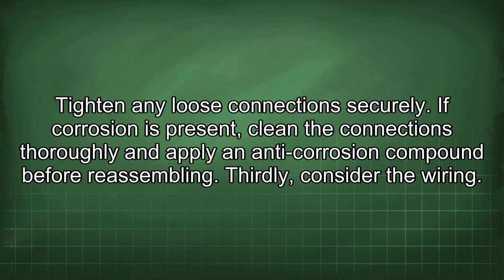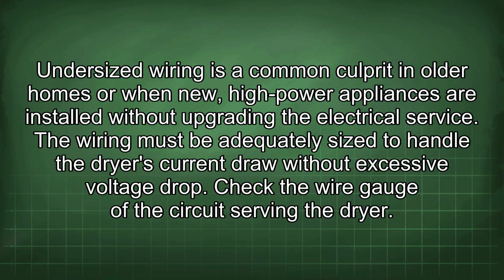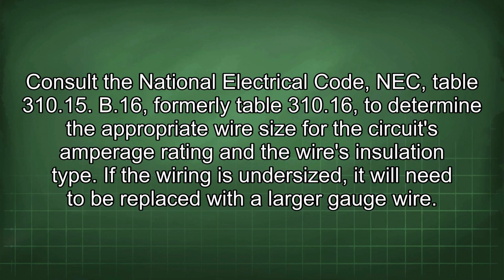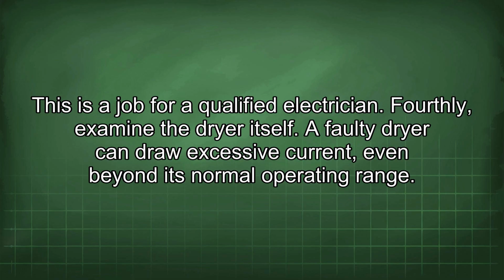Thirdly, consider the wiring. Undersized wiring is a common culprit in older homes or when new high-power appliances are installed without upgrading the electrical service. The wiring must be adequately sized to handle the dryer's current draw without excessive voltage drop. Check the wire gauge of the circuit serving the dryer. Consult the National Electrical Code, NEC Table 310.15(B)(16), formerly Table 310.16, to determine the appropriate wire size for the circuit's amperage rating and the wire's insulation type. If the wiring is undersized, it will need to be replaced with a larger gauge wire. This is a job for a qualified electrician.